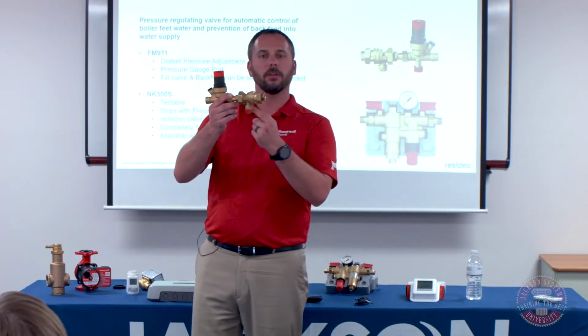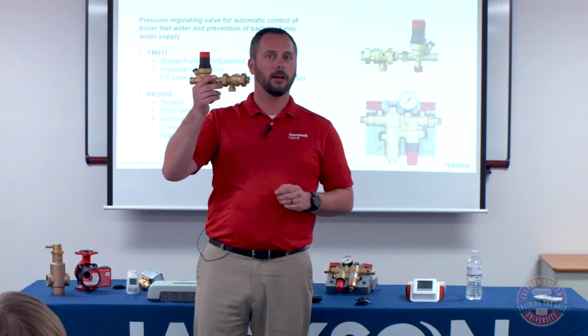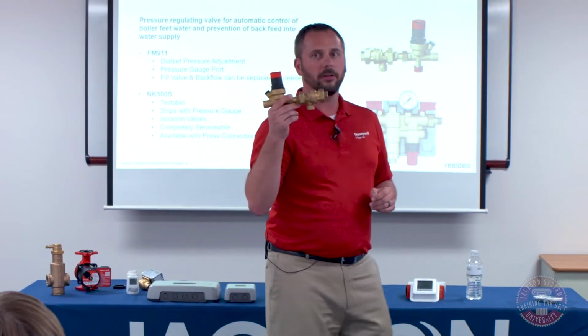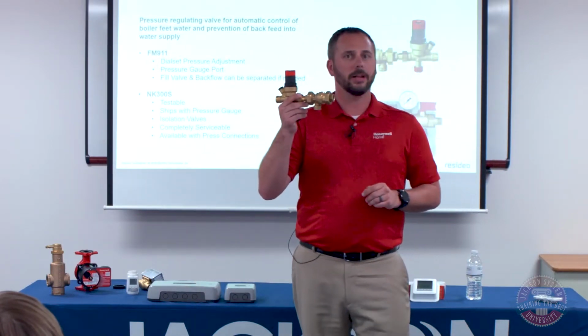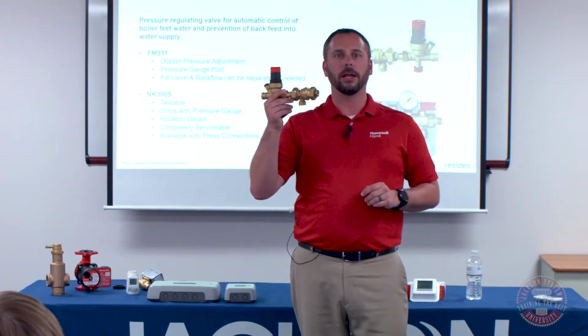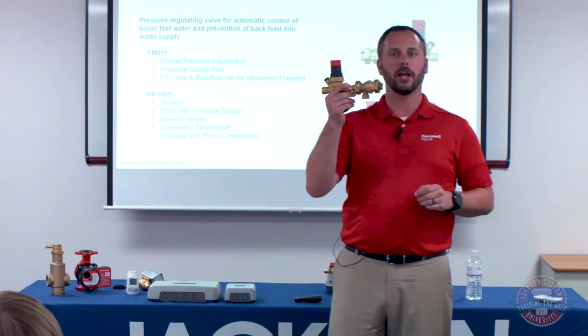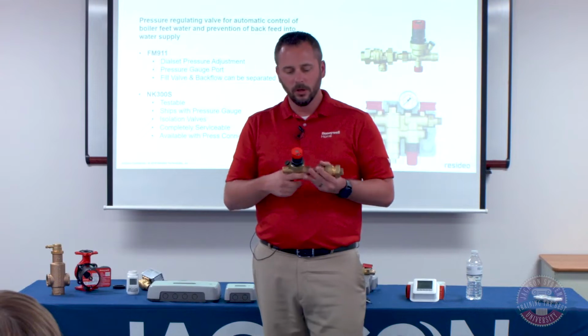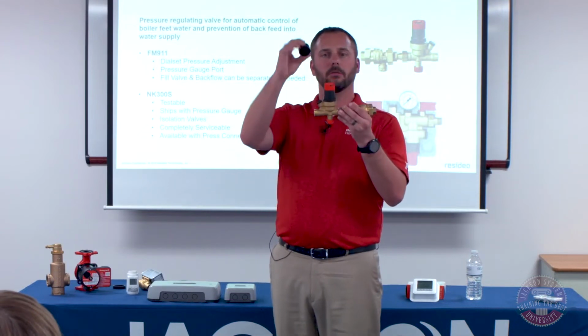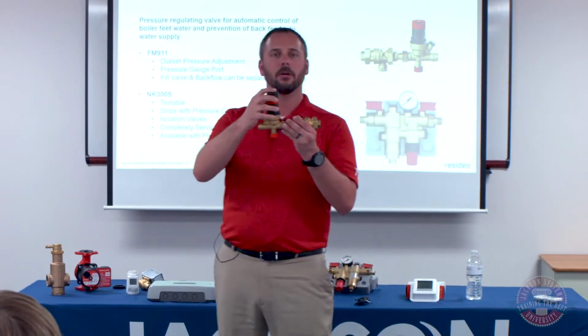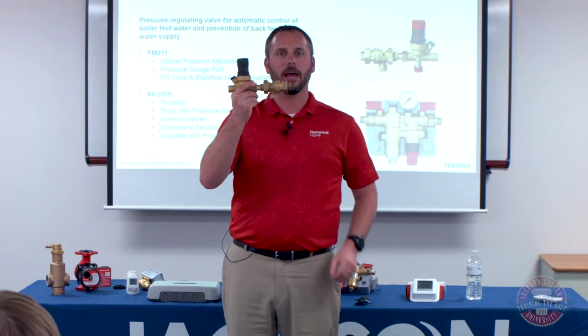Also, by code, this vent needs to be run to a drain. If you do run into an instance where one of these check valves fails, you're going to end up with water gushing all over the place. So make sure you run that to a drain with an air gap. We also ship it with this little plastic cap. Once you're done, you can put that on there.